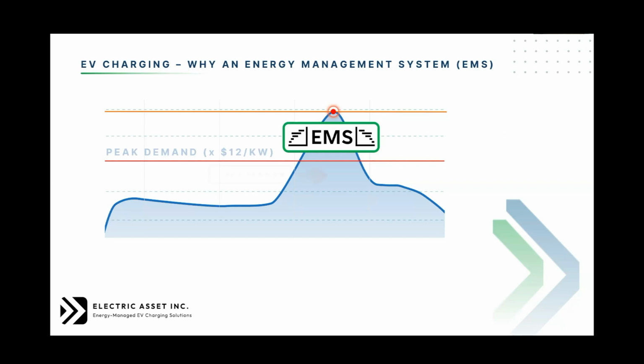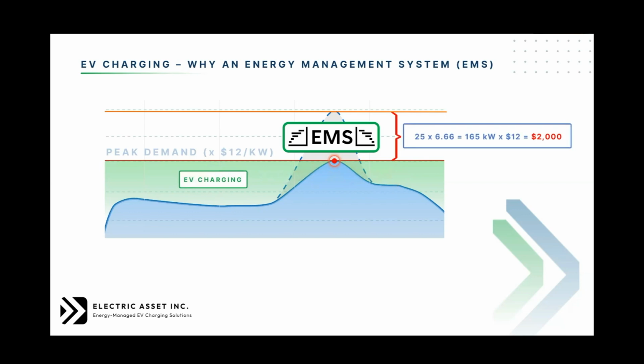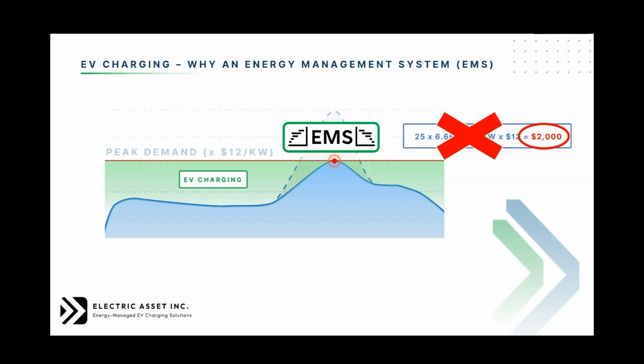So we set it at 100 kilowatts. When the same 25 vehicles come in, the EMS says this is going to drive up peak demand, so it limits the amount of energy going to the 25 electric vehicles. The vehicles may charge for a little longer, but this event saved $2,000 for this one incident. That's the value of having an EMS system.